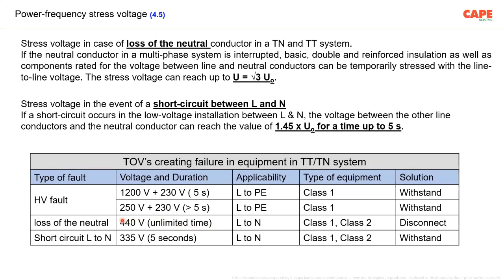Generally, in developed nations, this kind of the voltage, the time restrictions are given in the standard. Say, for example, 10 minutes or 30 minutes, not more than that. But if you have this kind of a system, in order to safeguard your equipment, please note that this is applicable for both class 1 and class 2 equipment. The only chance is to disconnect the supply. There are voltage relays available. You can put a neutral disconnection relay and you can trip your shunt trip, or you can put a contactor and trip the supply. So this is the safest method.